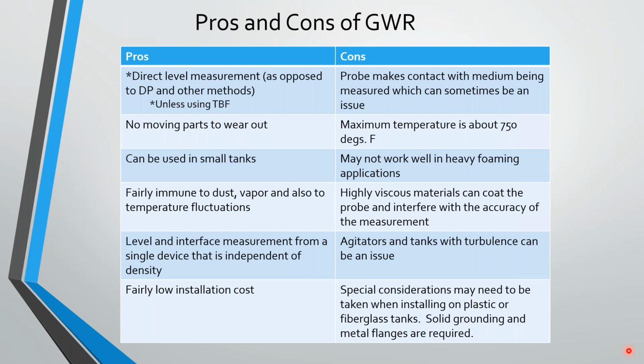If there are agitators and a lot of turbulence, again, we talked about possibly a stilling well would be required to overcome those issues. With guided wave radar, if we're on a plastic or fiberglass tank, we're going to have to make sure we have solid grounding. We're going to have to make sure we use a metal flange so that the signal after it comes back can stop at that metal flange.